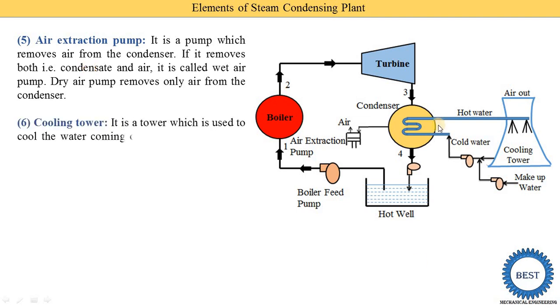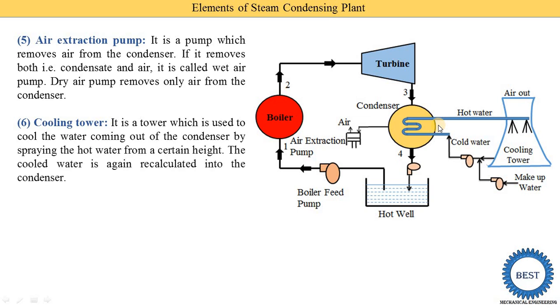The next component is the cooling tower. It is a tower used to cool the hot water coming out from the condenser by spraying the hot water from a certain height. The hot water is cooled by air supplied from the bottom sides of the cooling tower. Air absorbs the heat energy from the water and exits from the upper part. The cool water is again circulated into the condenser.